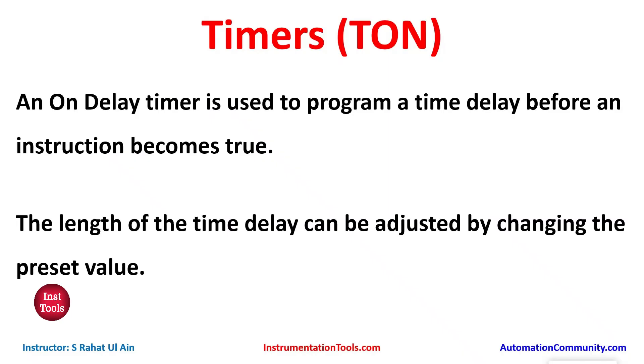An on-delay timer is used to program a time delay before an instruction becomes true. The length of the time delay can be adjusted by changing the preset value. For example, if the preset value is 5 seconds, when we turn on the input, the output will turn on after 5 seconds — so it delays before the instruction becomes true.